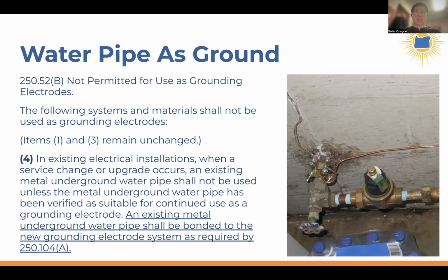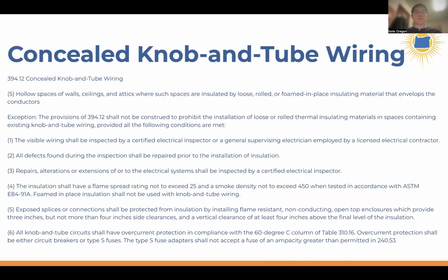In addition, you need to actually put in a real grounding electrode. That's because a year or two down the road, that metal pipe in the yard might burst, and when you hire a plumber to change it to plastic, suddenly your system is not grounded. That's why, during an upgrade, they want the ground also tied to a grounding electrode.